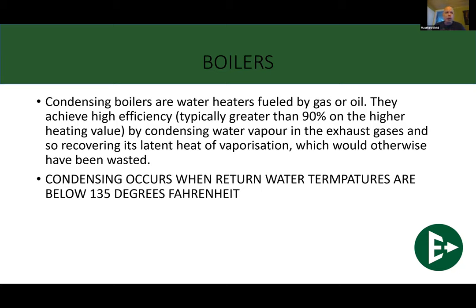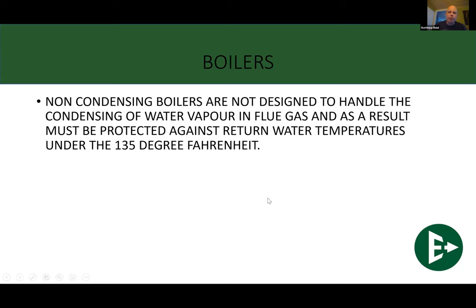Downfired heat exchangers are a really good way to make things condense, where your front-fired heat exchangers are also quite good, but you just tend to sweat more out of a down fire. Gravity is a wonderful thing, and use it when you possibly can. Again, as I mentioned before, condensation usually occurs when you're right around that 135 return water temperature mark. So if you have non-condensing, make sure that you are well above that in your return water temperature.